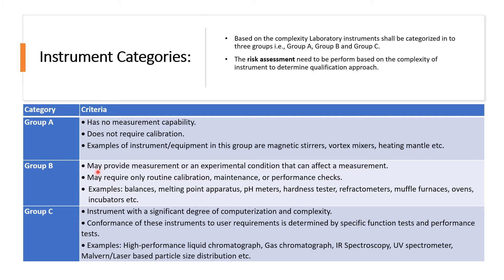Now Group B. Group B instrument equipment may provide a measurement or an experimental condition that can affect a measurement — meaning there should be some kind of reading or results, so it will generate some kind of data. Group B equipment may require only routine calibration, preventive maintenance, or performance checks. Examples of Group B instruments include balance, melting point apparatus, pH meters, hardness testers, refractometers, muffle furnaces, ovens, incubators, etc.